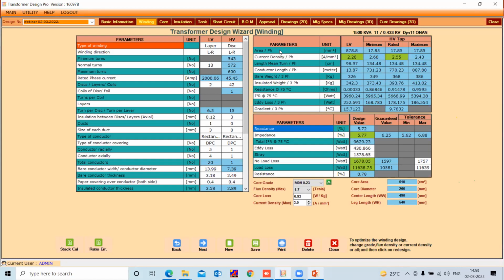Before I could even finish explaining the first table, it seems that the design is completely ready. Still, I will explain the whole table. The area per phase is given for both windings. The current density per phase is given. The length of mean turn is given. The conductor length is there. The bare weight for all the 3 phases in kilograms is given. The insulated weight, the bare weight plus the insulation, is what you see for the LV as well as the HV winding.